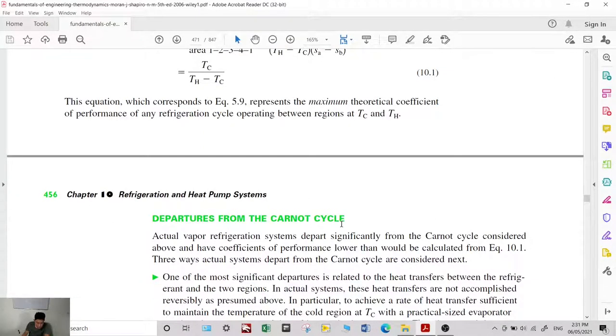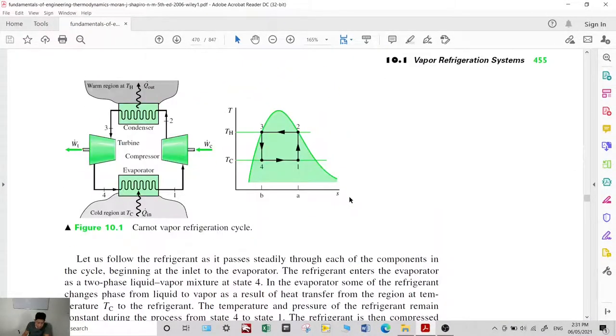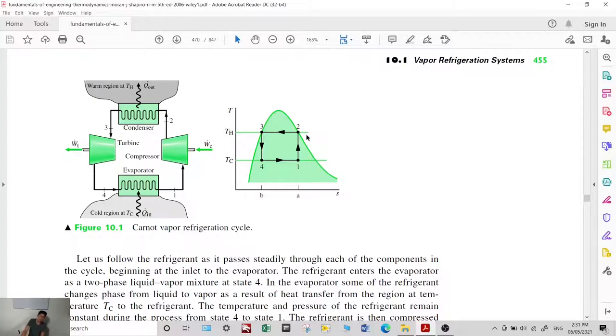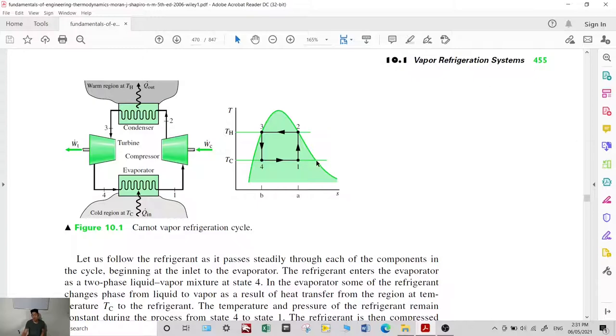Now let's discuss departures from the Carnot cycle in the vapor refrigerant cycle. One departure is at point 1: in an actual refrigerant cycle, this is what you call wet compression, meaning you are compressing both liquid and vapor. This has detrimental effects on the compressor. In actual compression systems, the refrigerant is allowed to reach saturated vapor or superheated vapor to eliminate wet compression.